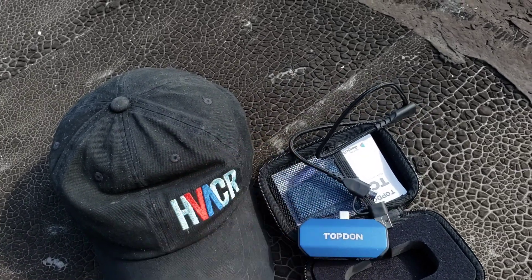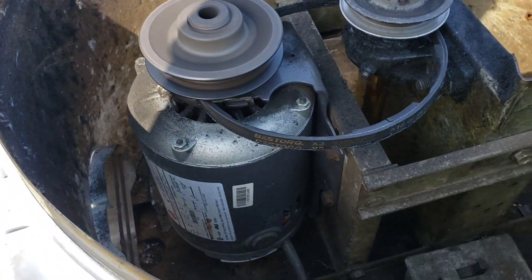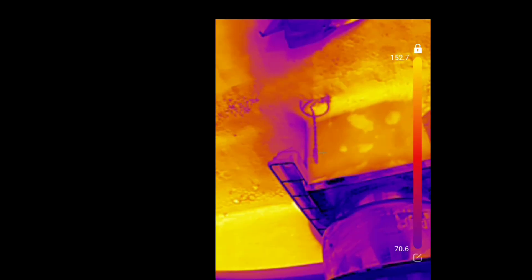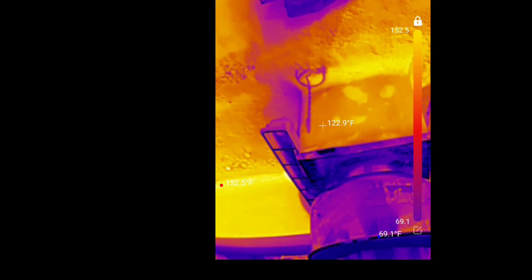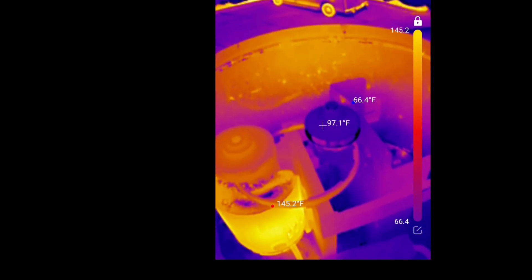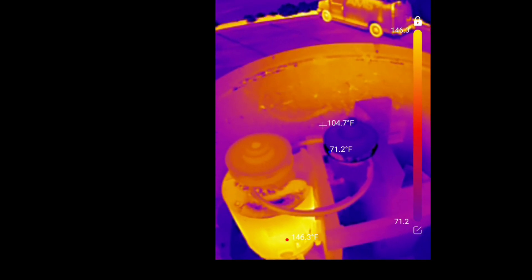Here's our exhaust motor — the belt broke, no big deal, motor's not seized up, looks like a fairly new motor. Before I do anything I'm going to turn the thermal device on and see how hot it is. Here's the TOPDON app — we'll open the thermal imaging section. It looks like we're upside down because I'm using the male-to-female adapter, so let me rotate it. There we go — there's our motor running at 143 degrees. The pulley, for comparison, is about 96 degrees. Look at that — white hot.